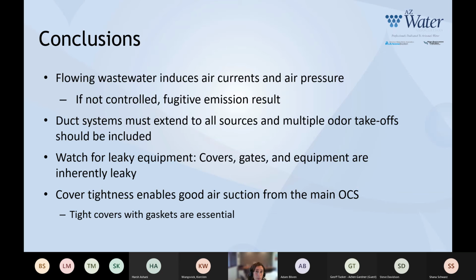So the conclusions from this presentation are that flowing wastewater induces air currents and air pressures. If you don't control it, if you don't find a way to draw it out, you might get fugitive emissions, and that can become really important when you're located next to a recreational facility, for instance. Duct systems must extend to all sources, but you might want to consider multiple takeoffs. As we saw, there were some locations where we had just one takeoff, and we added something to the other side of the channel that helped draw all of that foul air.